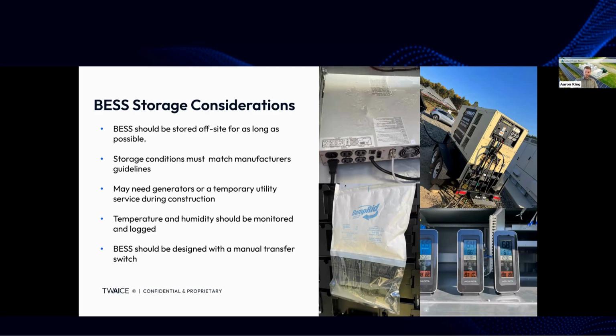It's also very common to bring in generators to run the thermal management systems while the batteries are stored, especially in particularly hot or cold environments. On the top left is an example of a project where there wasn't proper sealing and humidity control in one of the control cabinets, and you can see there was water damage that caused delays during commissioning.